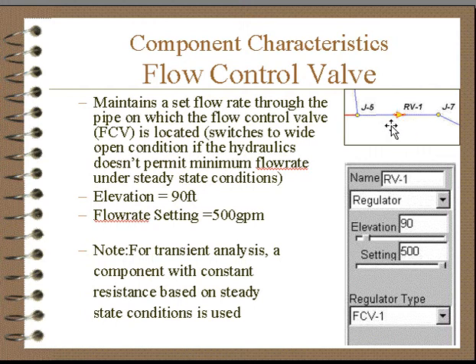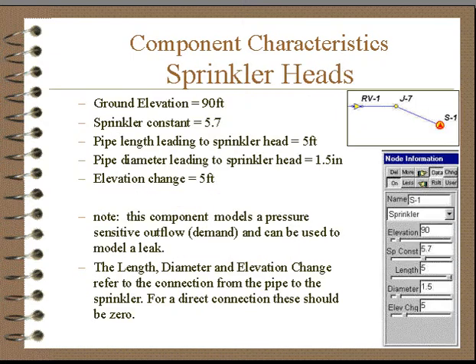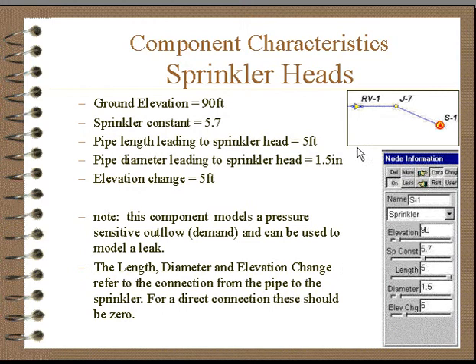A flow control valve works the same way — there will be a pressure drop, flow will be the setting, and that gives us the resistance to use in the transient analysis. Sprinkler heads are basically devices that model a pressure-sensitive outflow and these can be modeled in transients. These devices will remain at a constant resistance throughout the transient. If you want a situation where the resistance changes, this should be modeled as an active valve and not as a sprinkler.